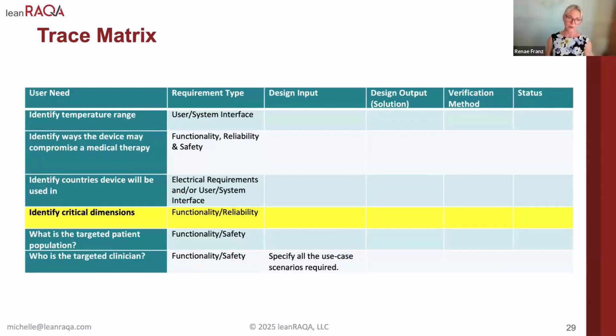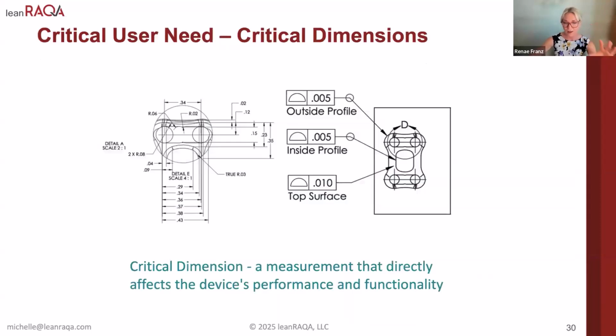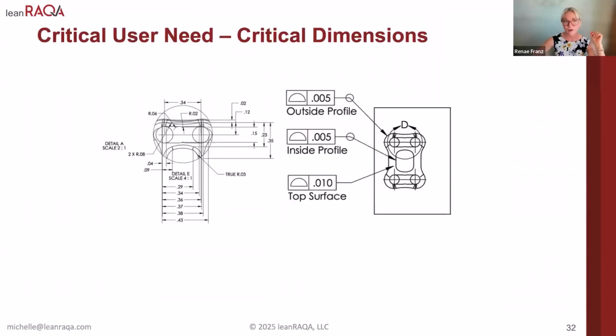So going back to that trace matrix, in addition to all of the different regulatory and consensus standards that you need to integrate into this, if you're designing a device, you also need to identify critical dimensions, and you really need to do that up front. And here's why. I should take a minute to explain what a critical dimension is. It's a measurement that directly affects the device's performance and functionality. And not a lot of people think about that initially when they're designing a device. So what could possibly go wrong?